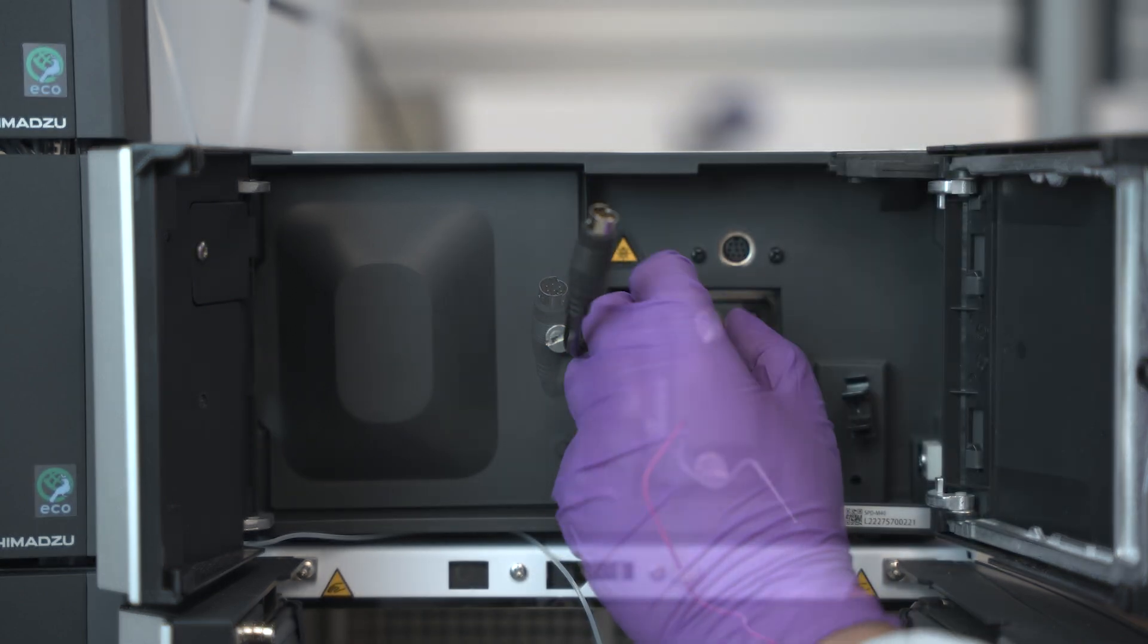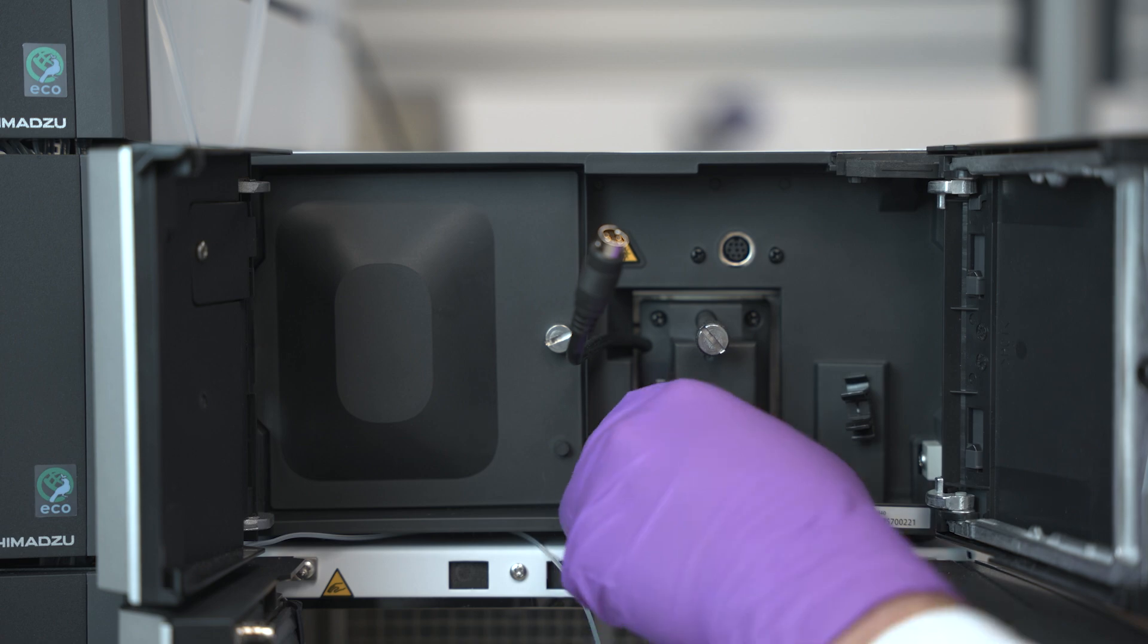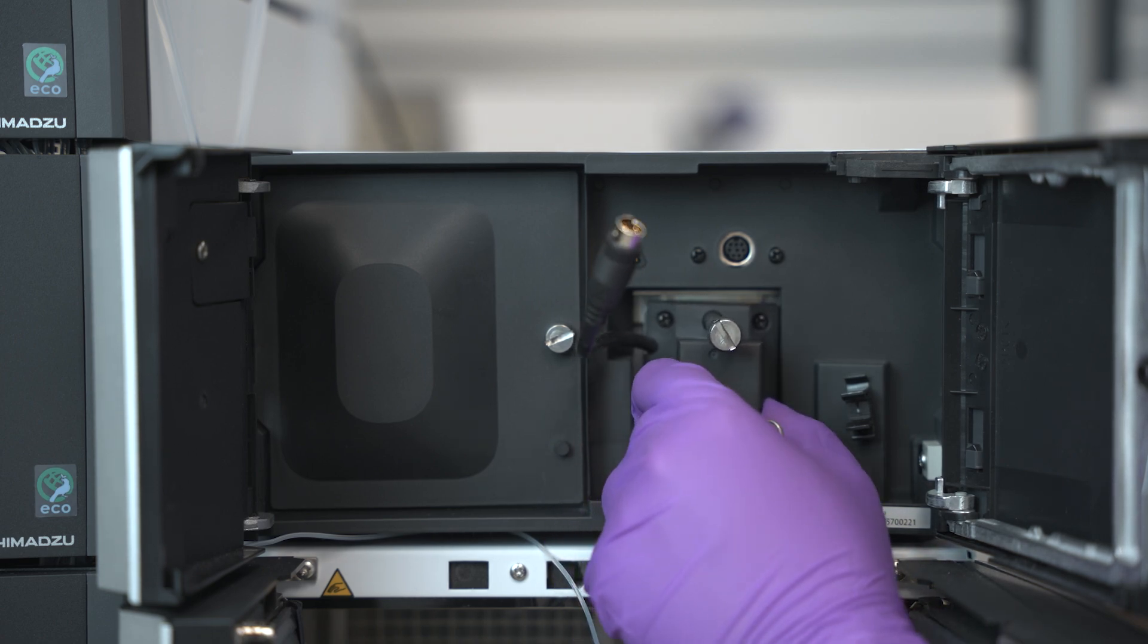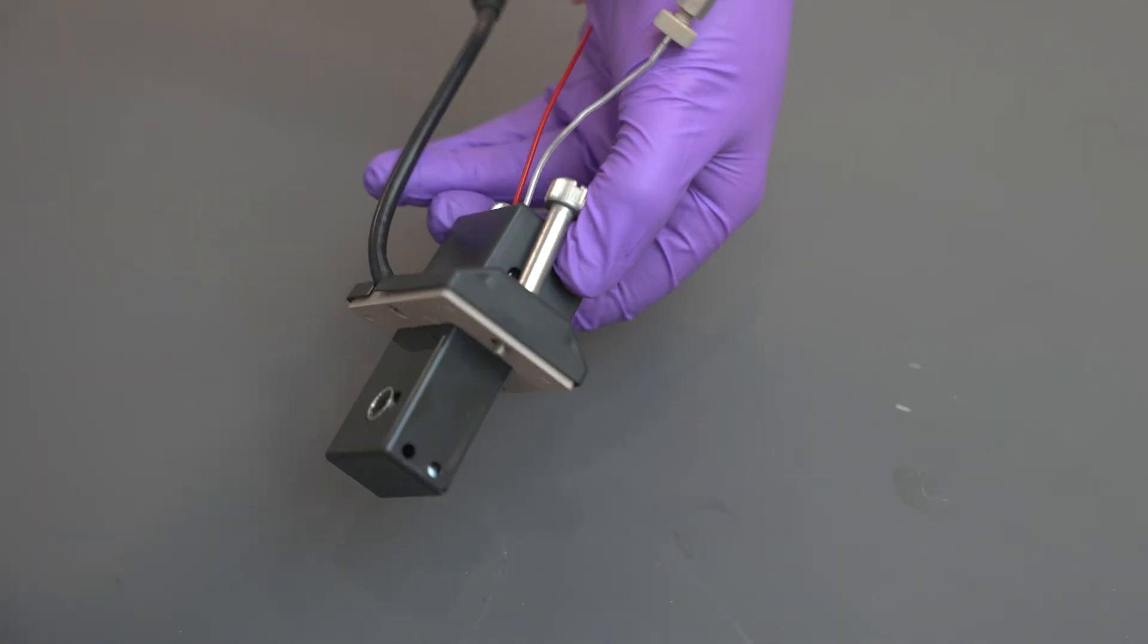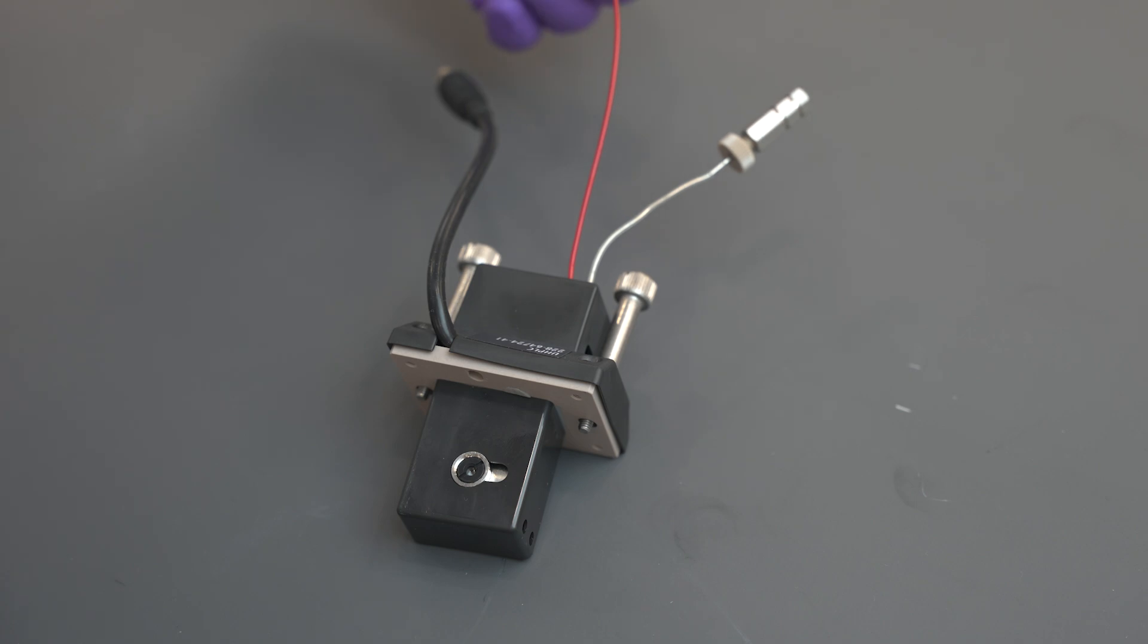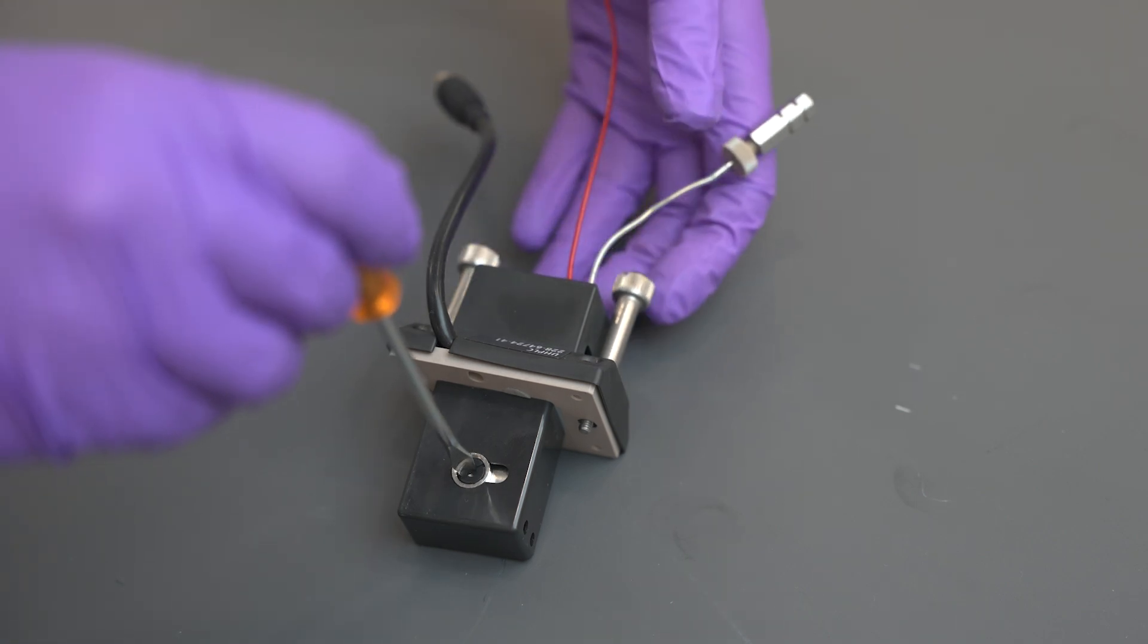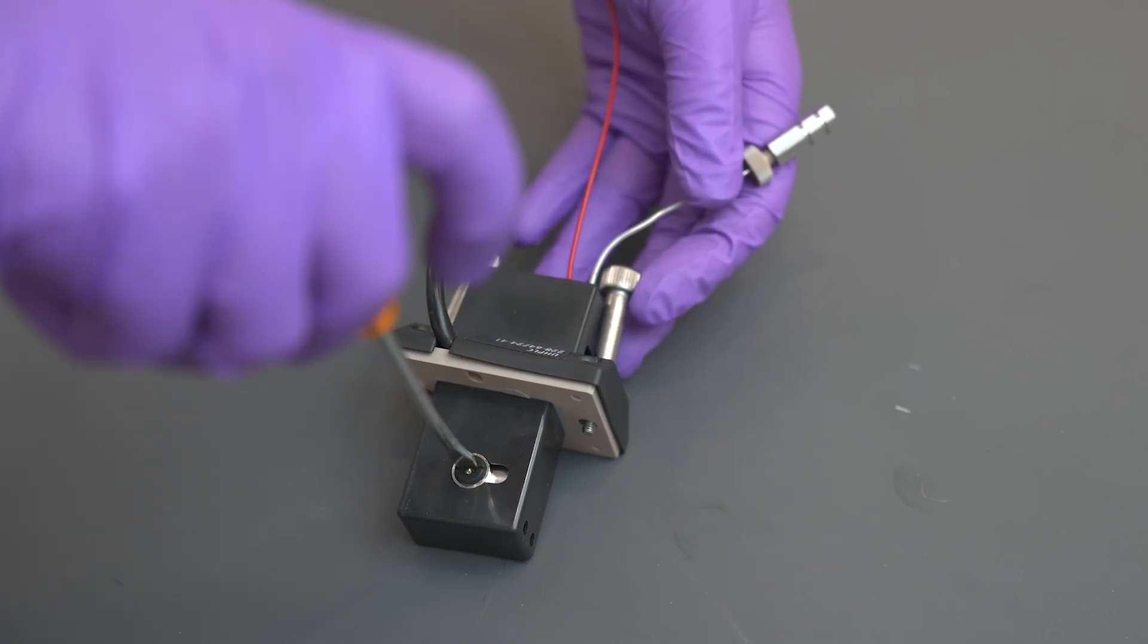Loosen the two cell mounting screws and pull the flow cell out. Remove the left and right set screws using the flathead screwdriver. Take your plastic tweezers and carefully remove the lenses and gaskets.